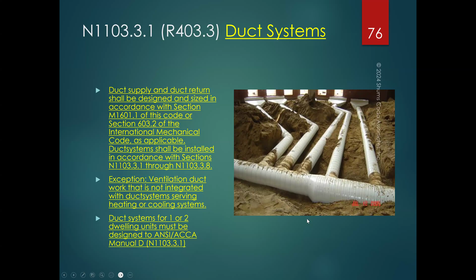Systems for 1 or 2 dwelling units must be designed in accordance with ANSI/ACCA Manual D. So that's what we're looking for. With the 2021 and 2024 codes, we've been asking for Manual Ds to be submitted with the Manual Js. So we need a Manual J, D and S. S is just your equipment, but the D we should be looking for, and it should include the fittings on the design side. Whether you've got corners, turns, your boots, those kinds of things, those should all be included in your Manual D.